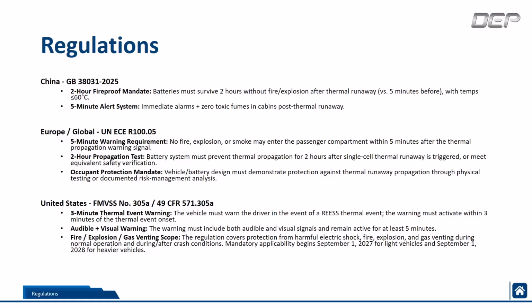United States is a little less than that. It's a 3-minute thermal runaway event warning, where the signal and the visual sensor, so pretty much the alert, has to be active for at least 5 minutes. And the regulation about harmful gases or explosion during the thermal runaway, normal operation, anything like that, is going to be applicable next year, in 2027.